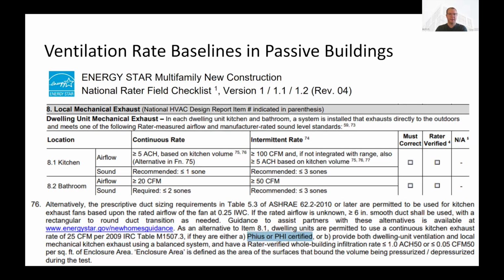When we look at passive building or potentially PHIUS or PHI certified projects, especially the PHIUS ones, they need to meet Energy Star certification criteria. And so I just cut out a few pieces in the Energy Star multifamily new construction checklist here, where when we specifically look at the kitchen exhaust airflow rate for continuous ventilation, it says greater than 5 ACH based on kitchen volume. And this is a really big thing to understand because that 5 air changes per hour ends up being very massive on even the smallest of kitchens.